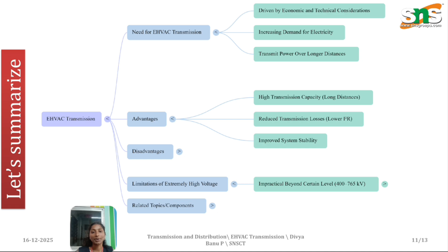Coming to the assessment: what is the main reason for using extra high voltage AC transmission? The main purpose is to reduce current and power losses. Bundled conductors are primarily used in extra high voltage, where instead of a single conductor, bundled conductors are used, in order to reduce corona and radio interference.